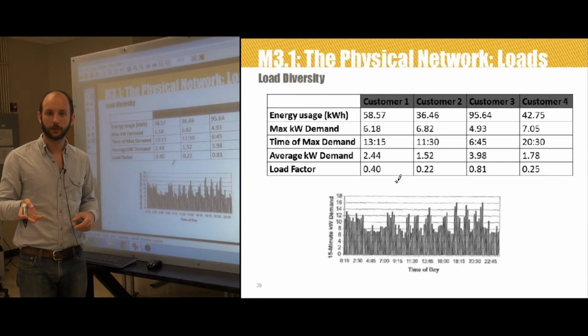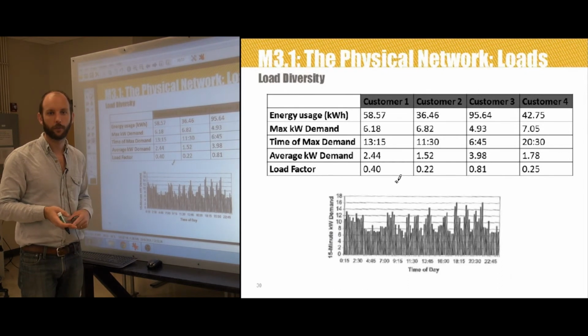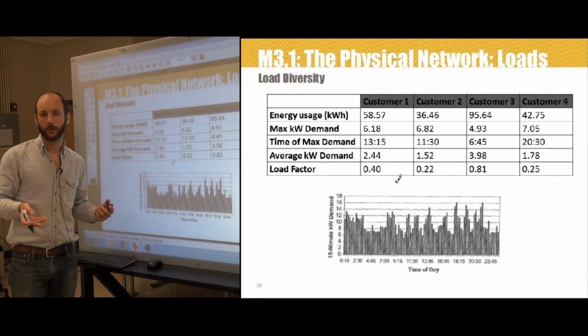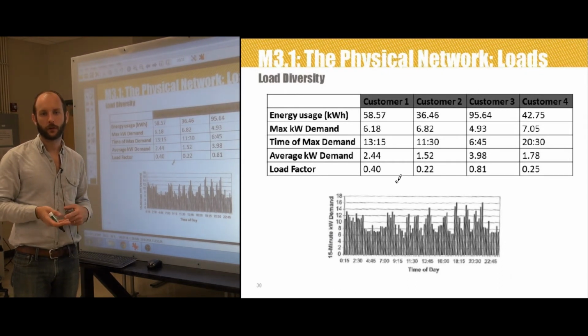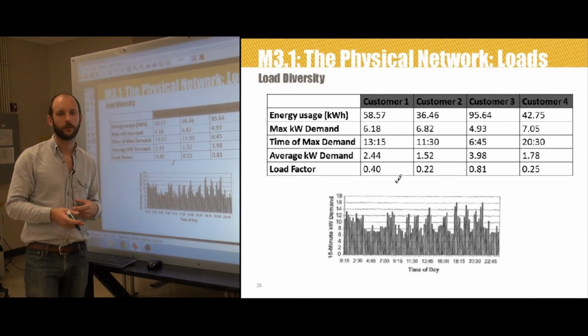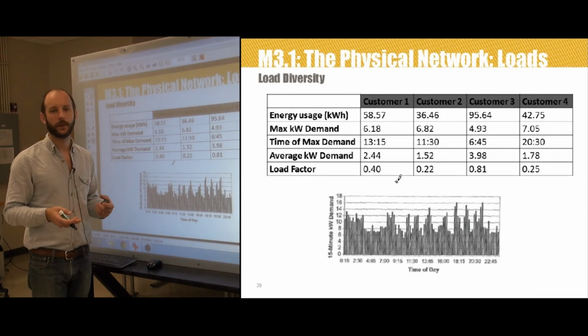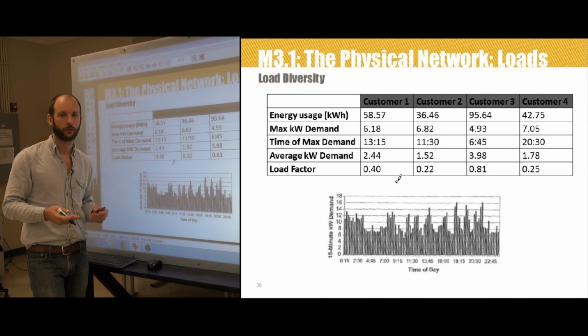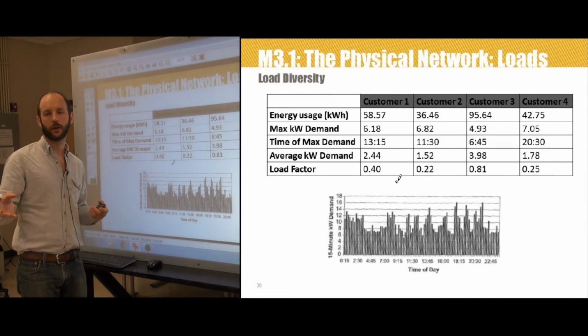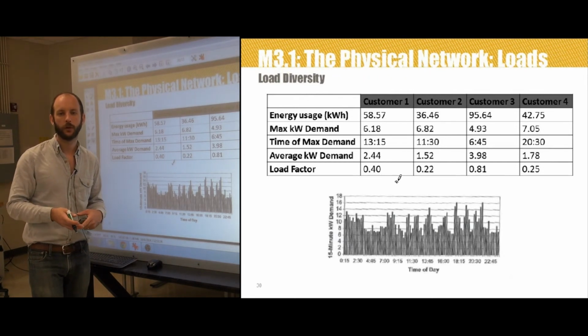Typically, multiple customers are going to be connected to the electric grid at a single point. For example, in a residential system, the transformer used in this application would be a distribution transformer. It's a step-down transformer used to convert the distribution level voltage down to a level appropriate for customers, and typically you'll usually have three customers connected to that distribution level transformer.